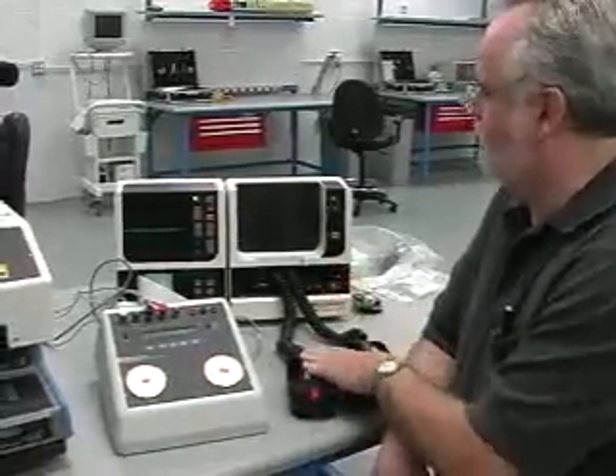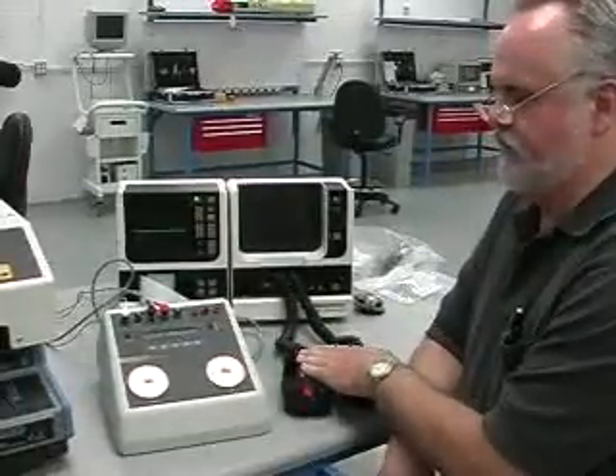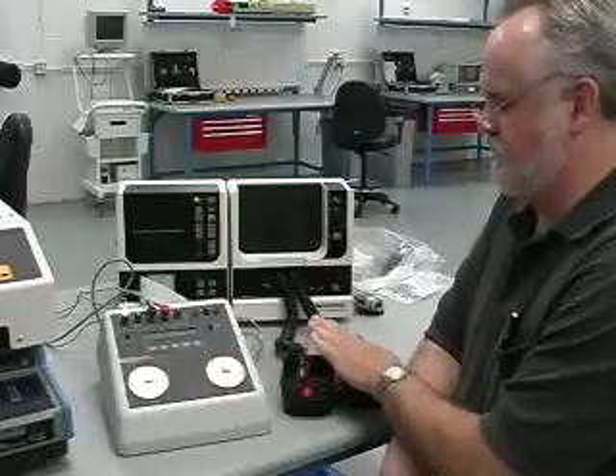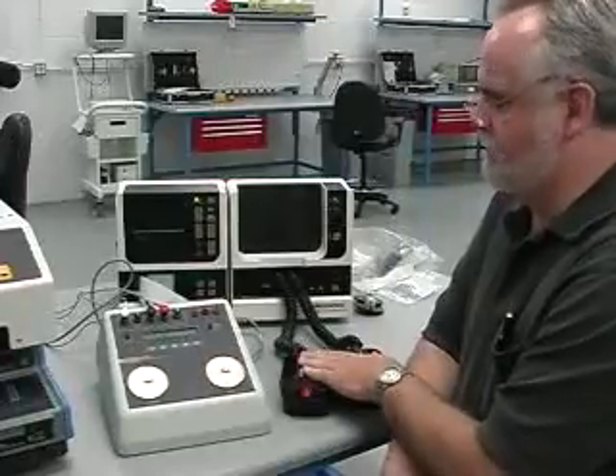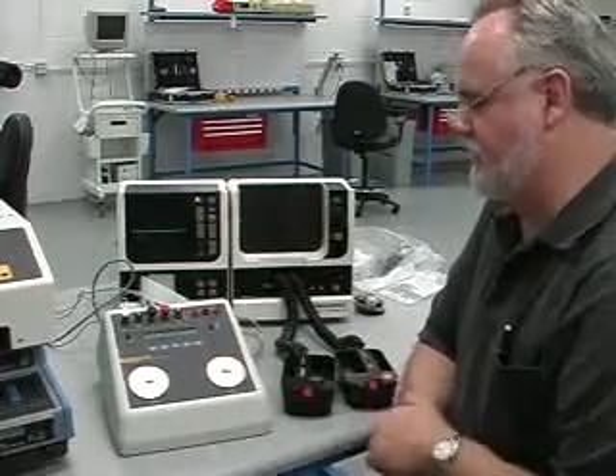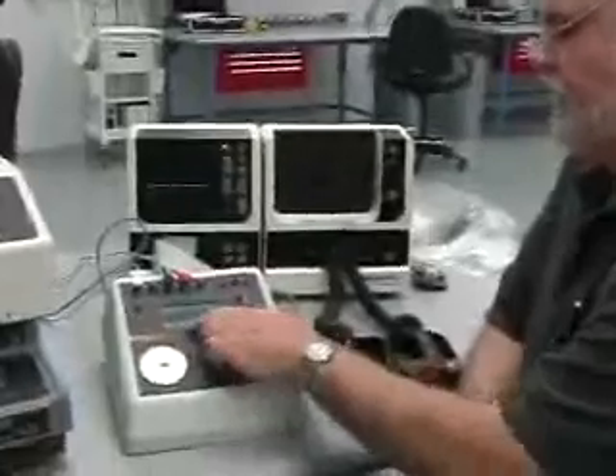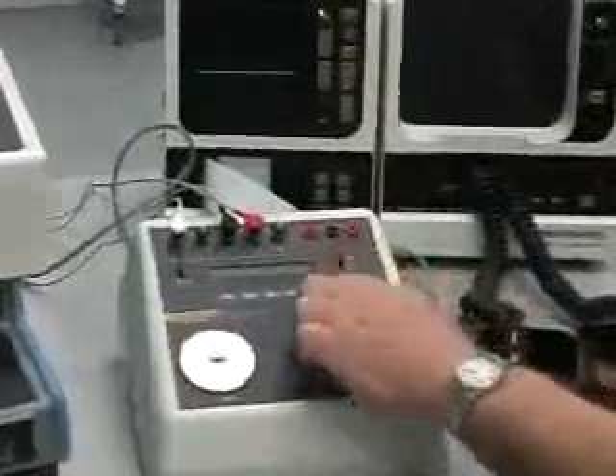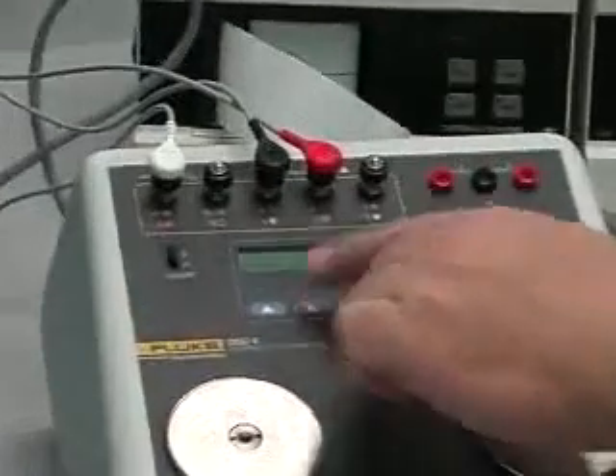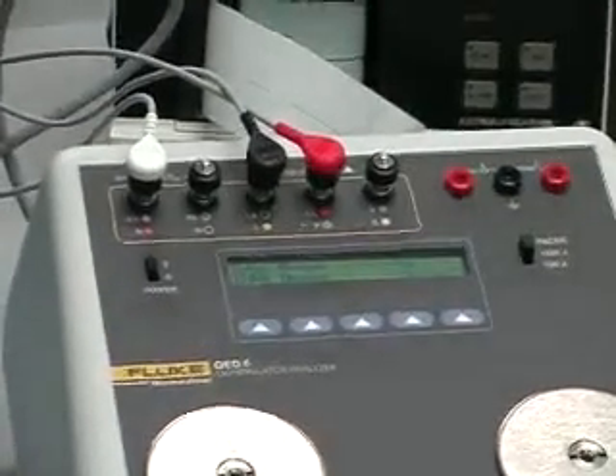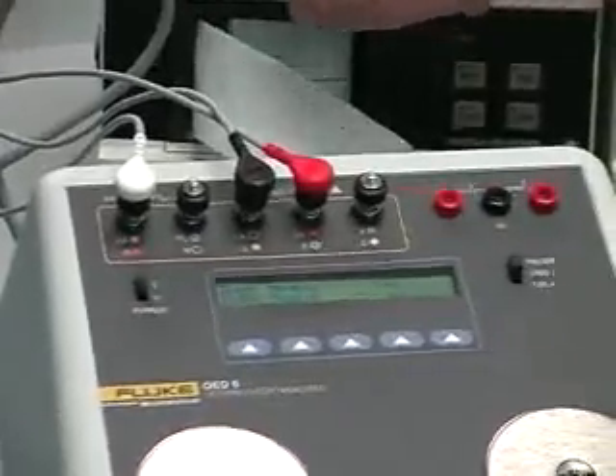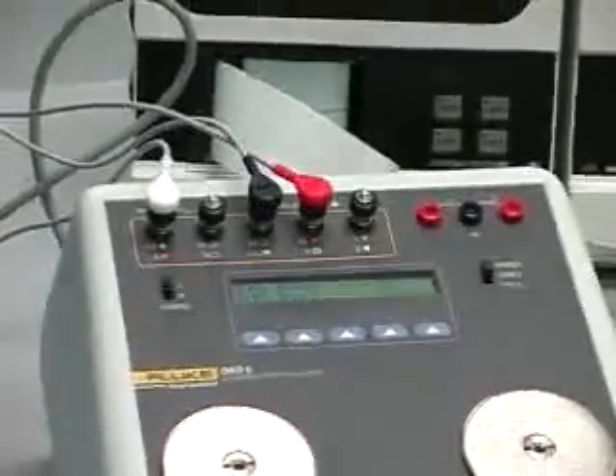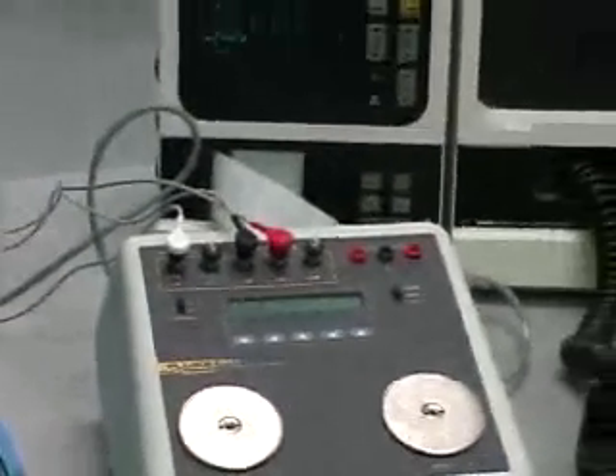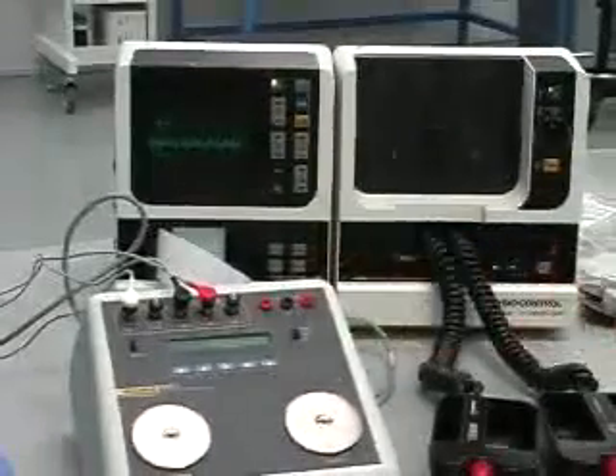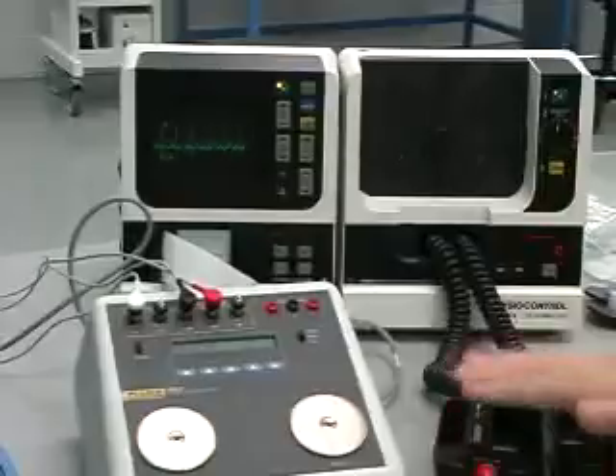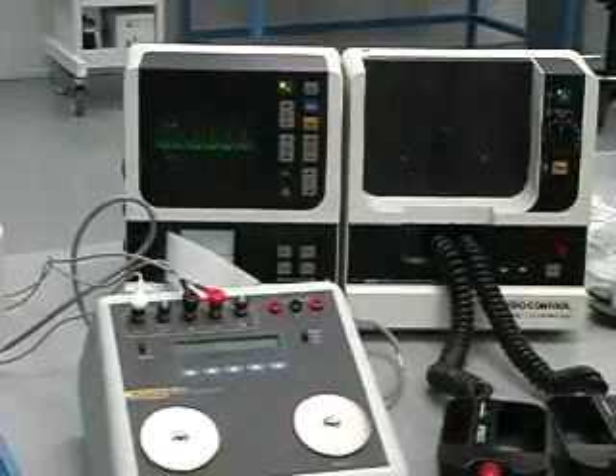Okay, so we've got a good operating defibrillator, good energy levels, and also good charge and discharge times. Now we're going to run the cardioversion test, or a synchronization test, as we had talked about. That's under the main menu 1. It's under sync, and with that, it does generate just a normal sinus ECG. And at this point, if I were to charge up the defibrillator and discharge it without any synchronization at all, who knows what that timing would be between the two. There would be nothing to tell the defib when to discharge.